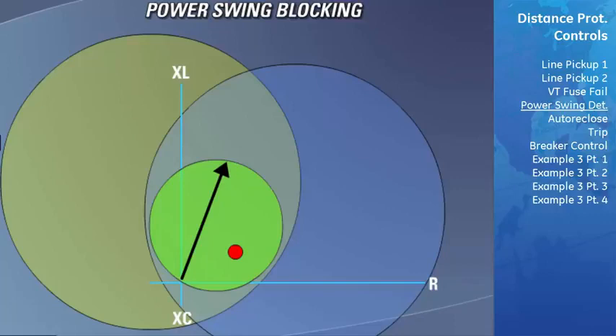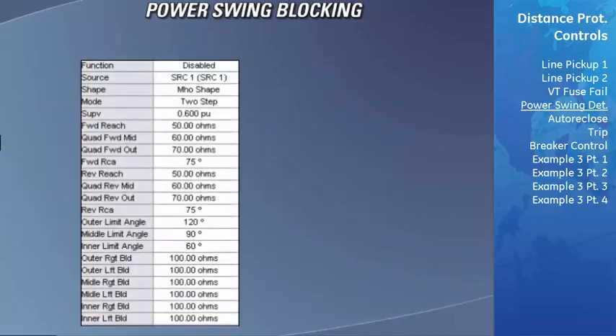There are 2 or sometimes 3 characteristic zones of the power swing blocking feature. The diagram shown here is a 2-step coordination example. The 2 zones in this diagram are the outer zone, which is the tomato shape, and the inner zone, which is the lens shape. The outer zone is what detects the power swing and sets the block of the distance element. If the impedance enters the lens shape, the power swing block stops considering this a power swing. However, it does hold the block signal on for a while to allow the impedance to leave, as will happen in a stable swing.